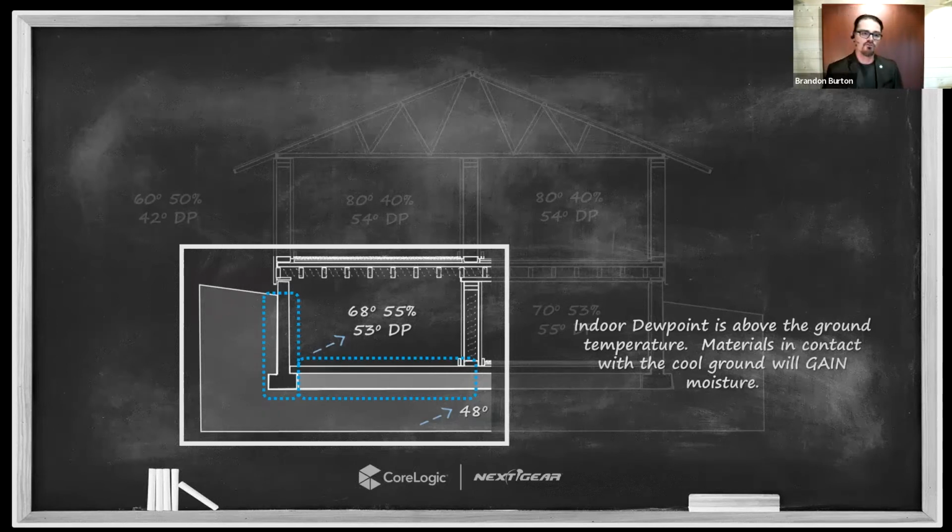And part of the reason I spend so much time really emphasizing this in today's episode and previous episodes is that we often overlook this. You know, we tend to go into an environment, we grab a moisture meter, we measure how wet a building material is, we take a couple temperature and humidity readings so we know what the affected air is, or maybe the outdoor air is, but we never step back and really appreciate the fact that the temperatures have to be appropriate to support drying. And dew point forces us to have that conversation, especially when we apply that 20-degree delta, right? It forces us to have that conversation. It also makes it relatively simple to ascertain from that discussion whether or not there's enough energy, if we just remember that 20-degree delta. Okay.